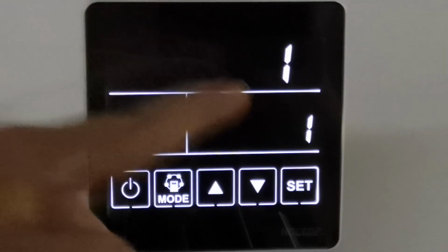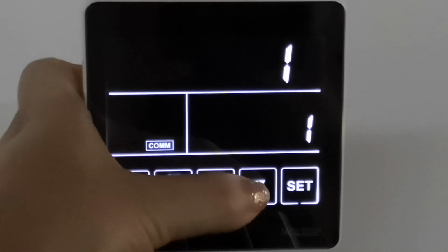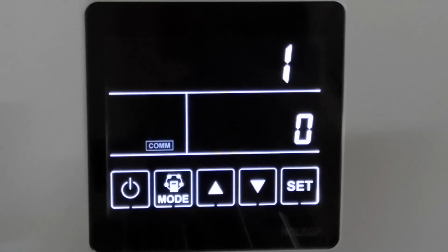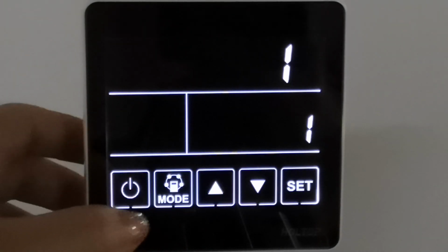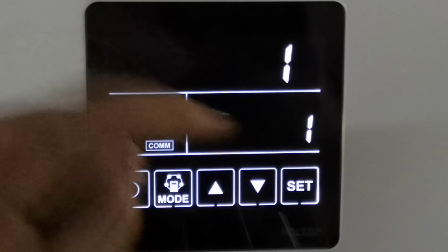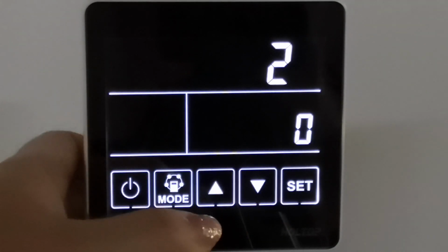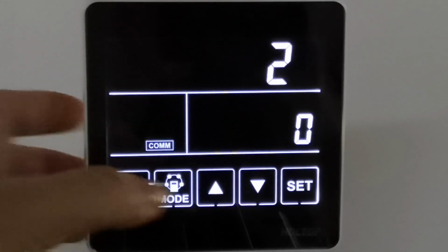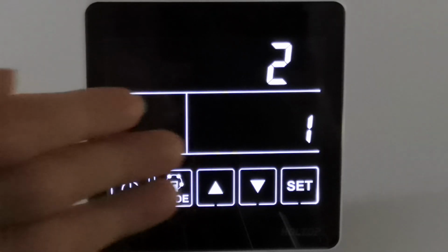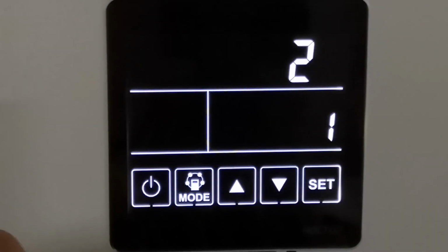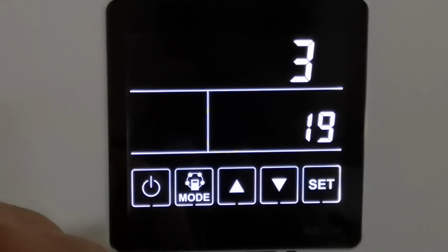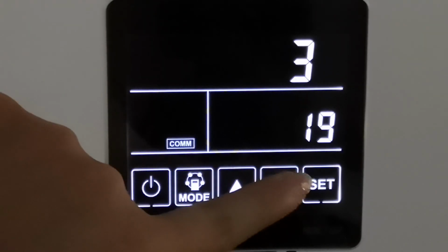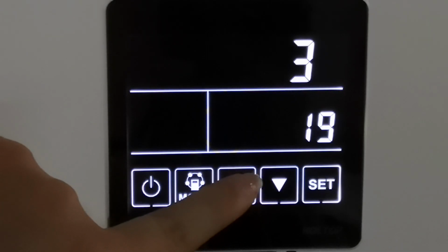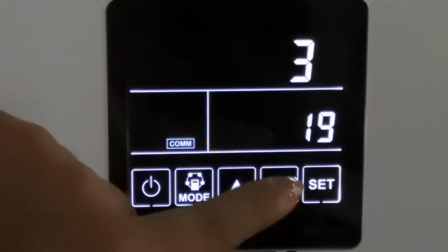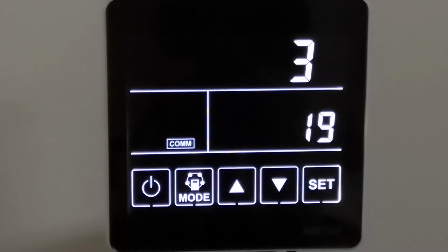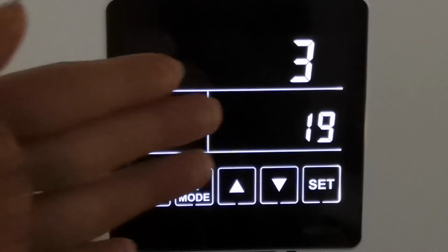Parameter 1 refers to power auto restart. 0 is invalid. 1 is valid. The default value is 1. Parameter 2 refers to the bypass function. 0 means manual operation. 1 means automatic operation. Parameter 3 refers to the bypass opening temperature. The temperature can be selected from 5 to 30 degrees. The bypass will be switched on automatically when the outdoor temperature is equal to or higher than the setting temperature. Let's keep it at 19 degrees.